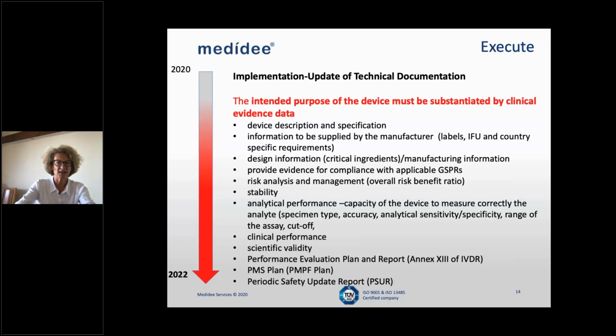Of course, as for the EER checklist, the legal manufacturer needs to show compliance with the applicable GSPR. So we will expect to have a GSPR checklist. Also, a risk analysis for each device and a risk management report, which has to make reference and a conclusion based on a disclosure of the residual risk, and also a statement on the overall risk benefit ratio. Stability is another important point, not only shelf life, but also in-use stability and transport stability.